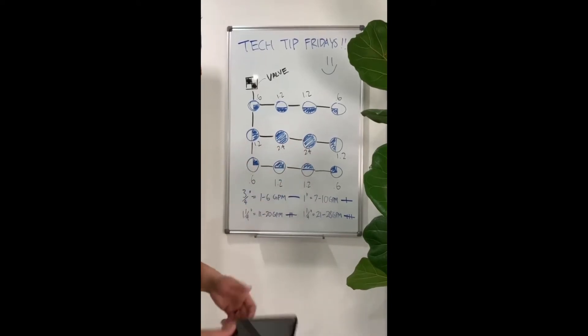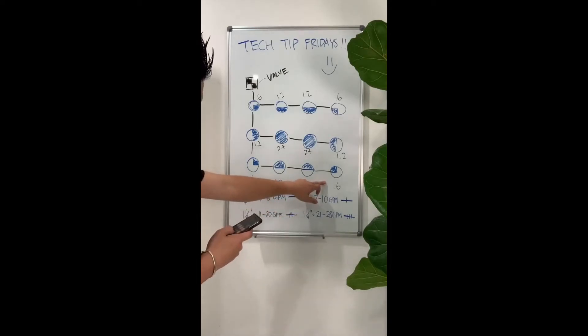So the way that we would do this is we would always want to calculate from the last head. So if your valve's up here, you want to work your way back and start adding your heads to figure out how many GPMs is going through that section. So we'll do 0.6 plus 1.2 plus 1.2 plus 0.6. And that's 3.6 GPMs that's going through this section right here.